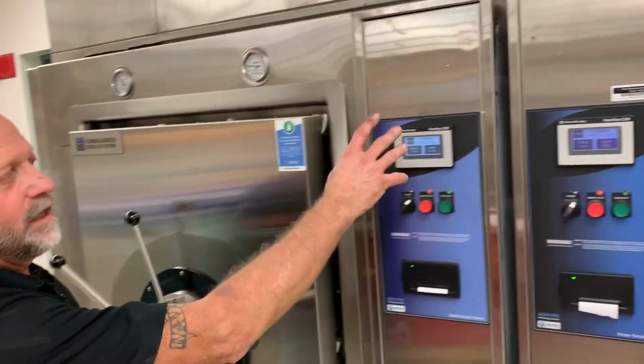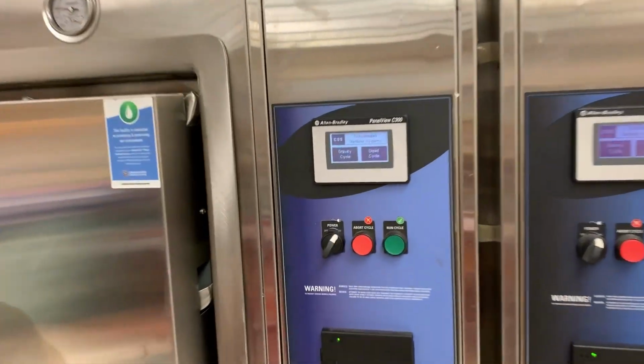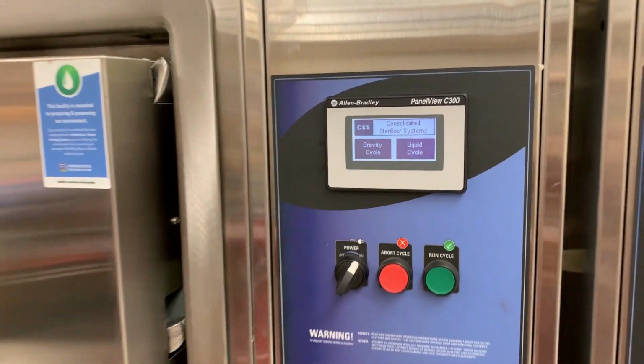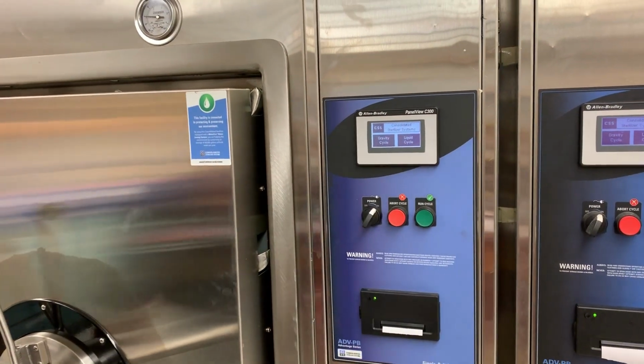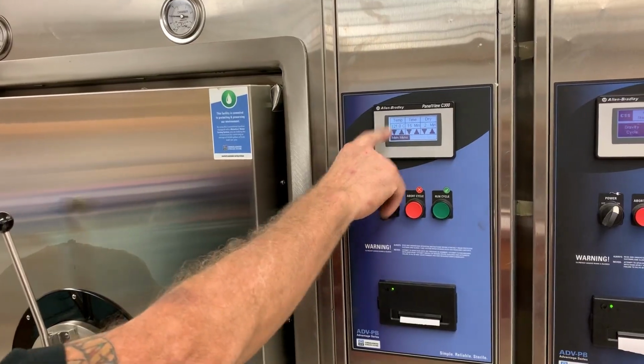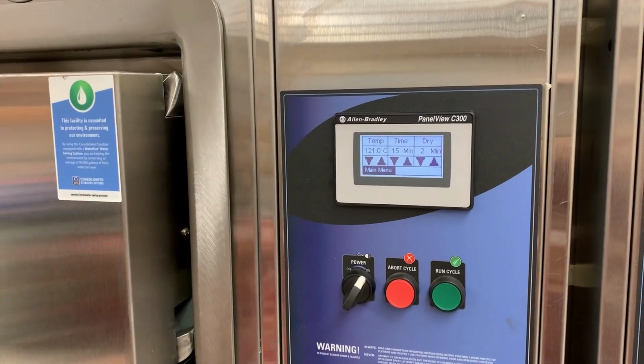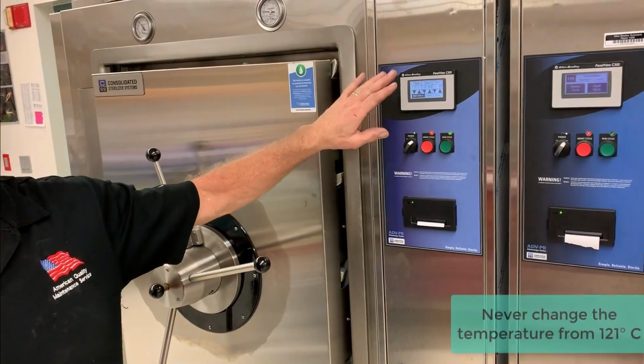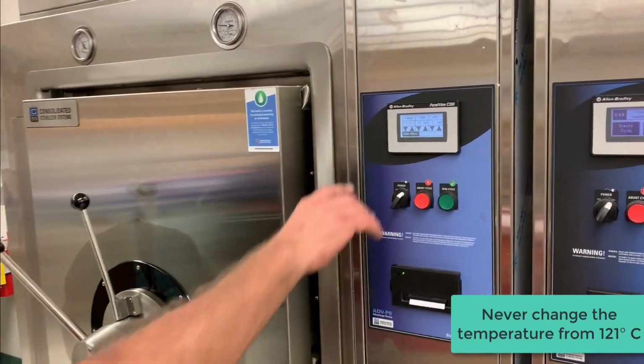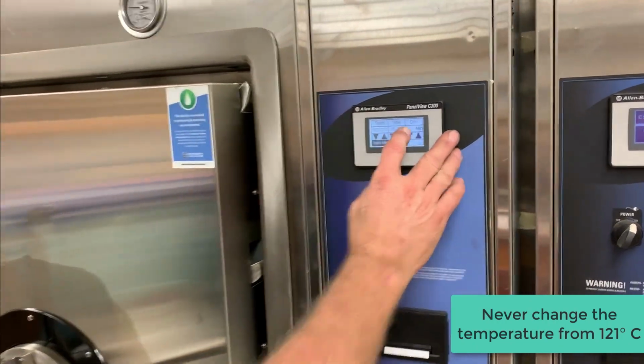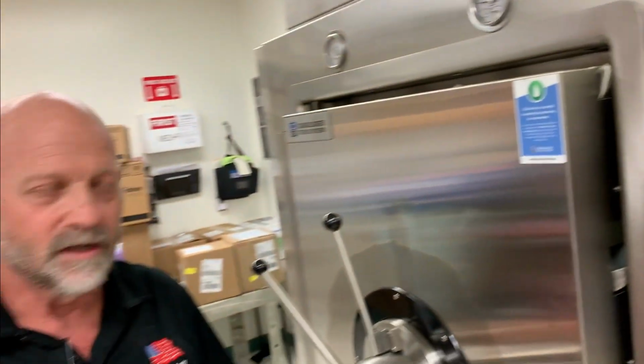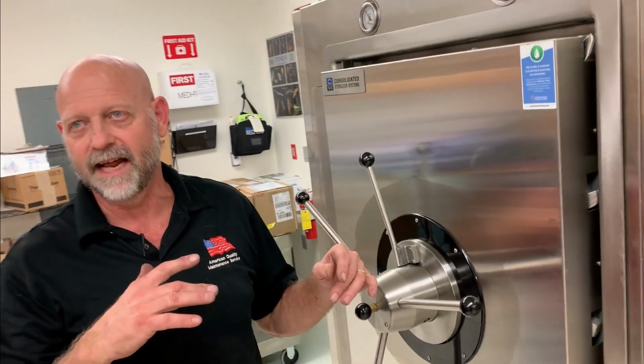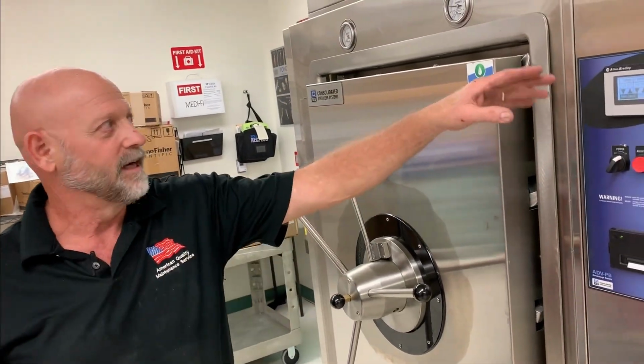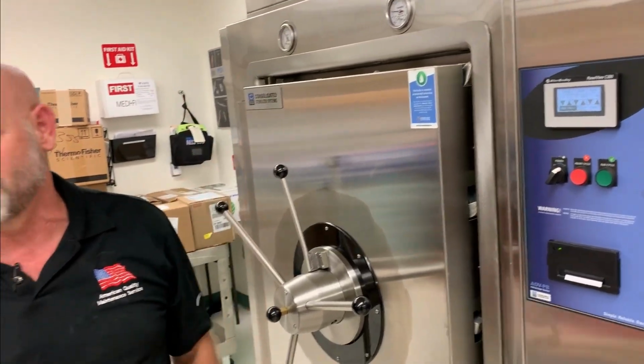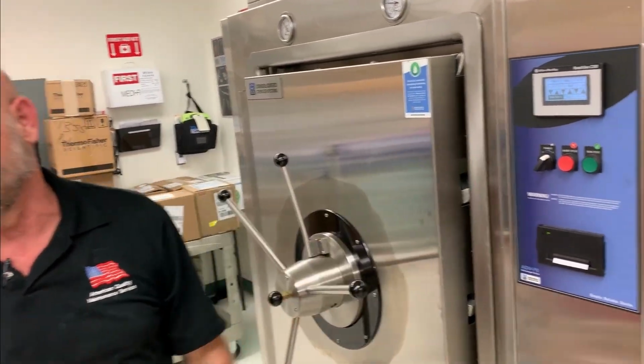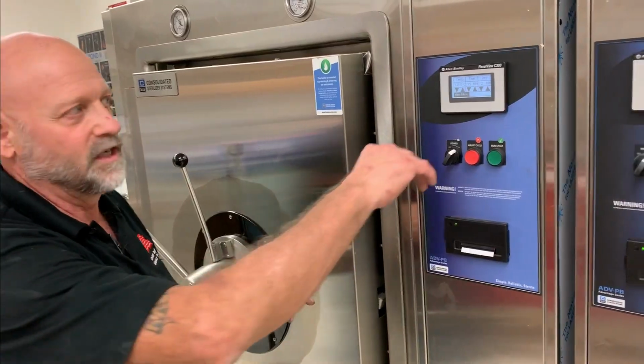On the settings, you have two different types of runs: a gravity run or a liquid run. In the gravity run, you press gravity. The temperature you never change. Nobody changes the temperature. The 121 never gets changed. What does get changed is time. You don't have to worry about pressure because the machine calculates that itself. It knows that it's going to run a chamber of around 18 psi for 121 degrees Celsius.